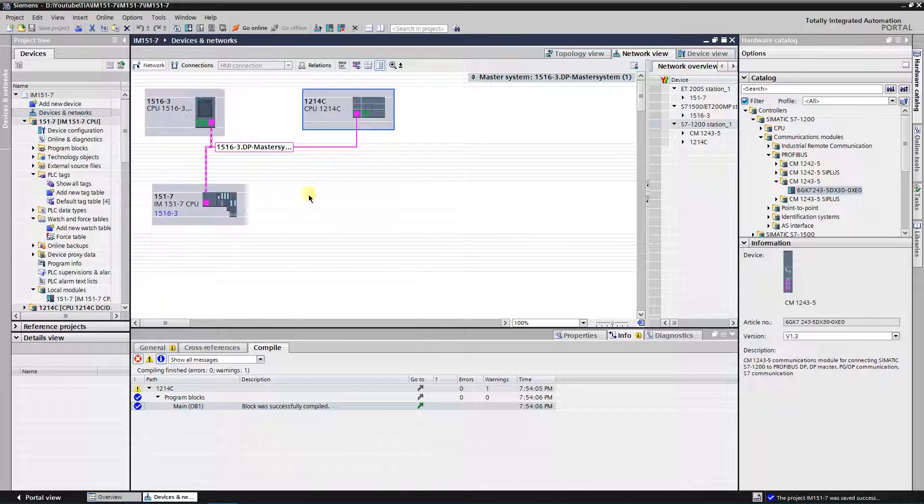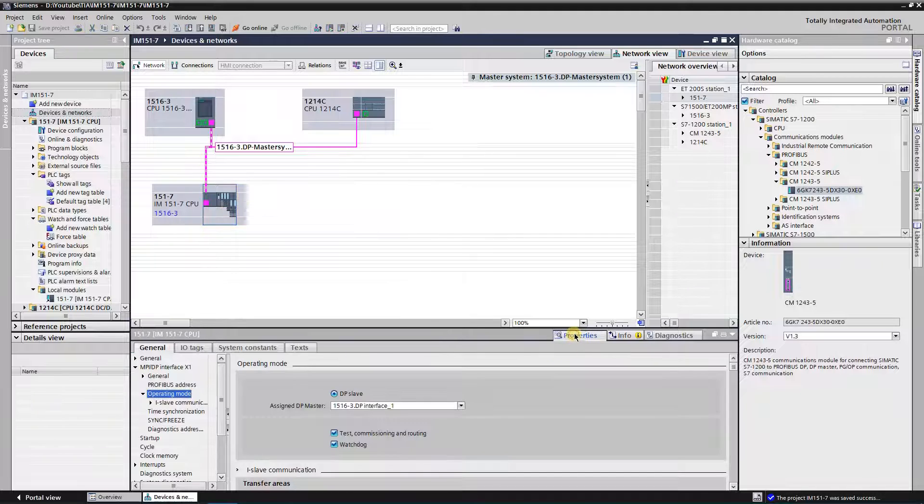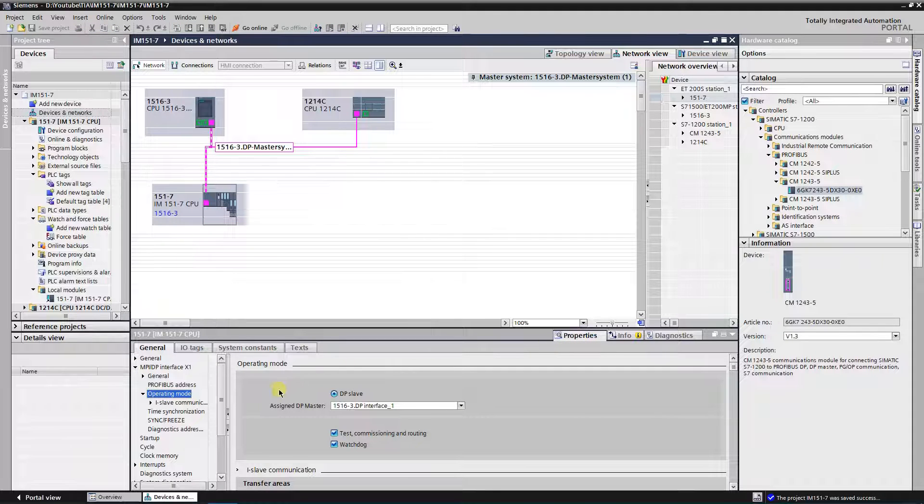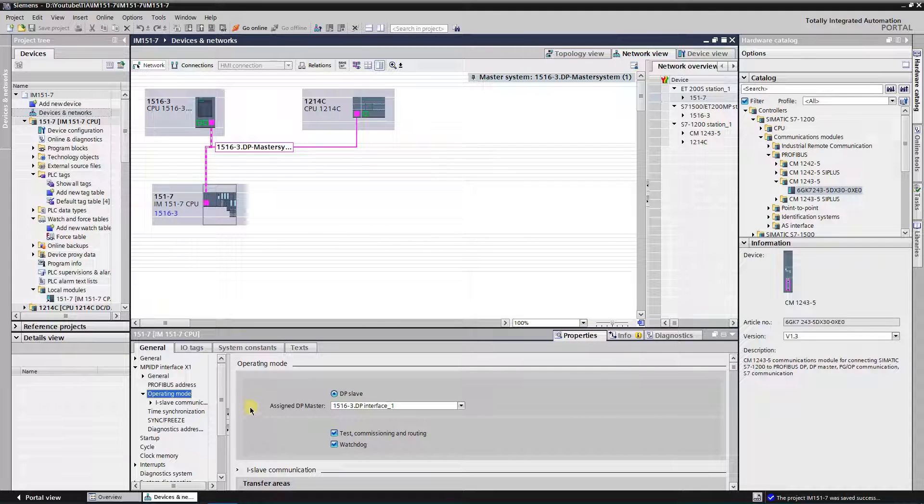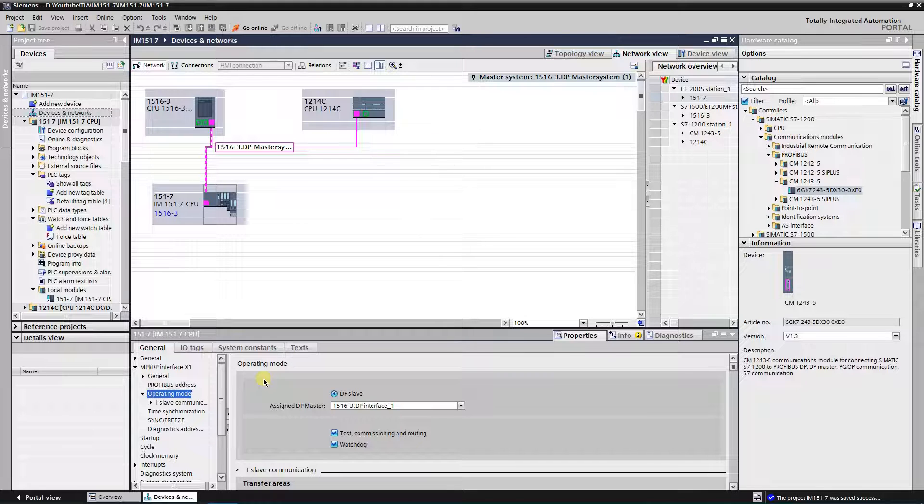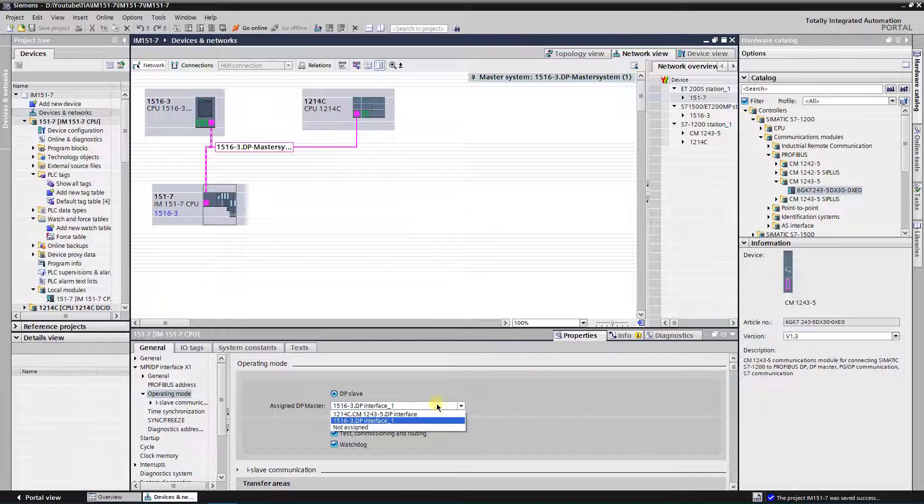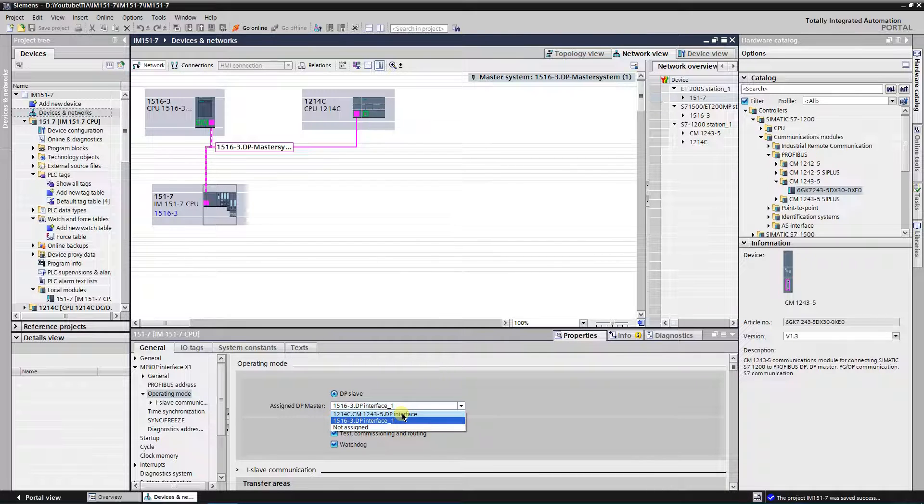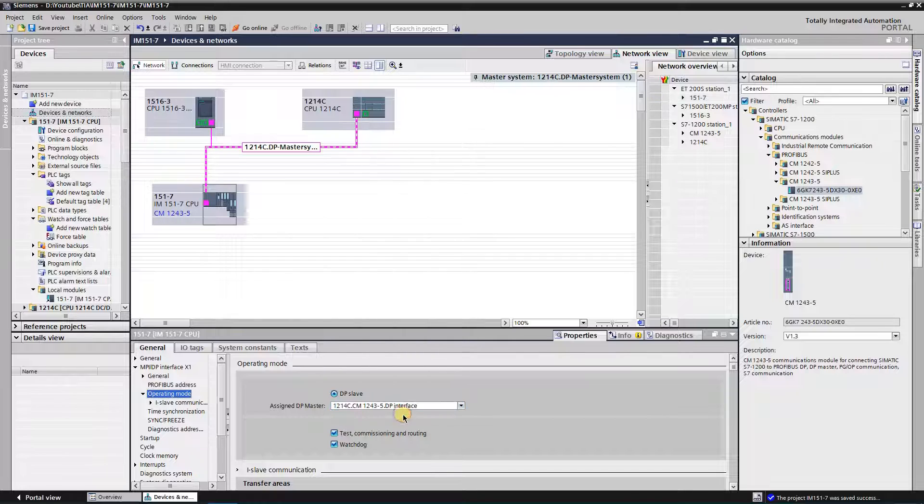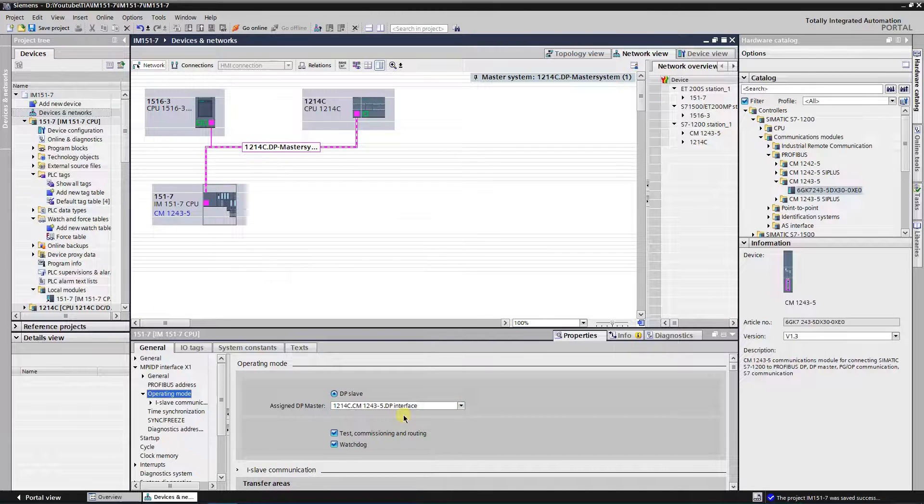Select IM151-7 CPU. Switch to the properties, General tab, MPIDP interface, operating mode. Currently, S7-1516-3 DP is assigned as master for IM151-7 CPU. Expand drop down list, and select 1214C as DP master. As you can see, IM151-7 CPU became an i slave of 1214C DP master system.